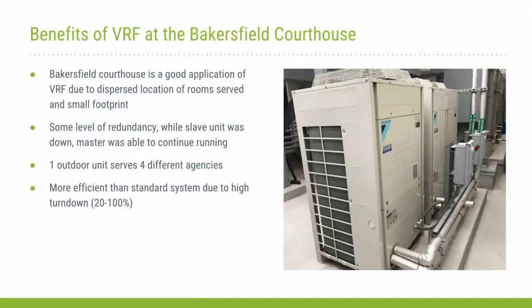So the benefits of the Bakersfield VRF installation have been due to the dispersed location of the server rooms and equipment rooms that it serves throughout the building, some on the first floor, some on the second floor. The runs for piping for a traditional system would not be a possibility in this location. One outdoor unit serves 4 different agencies: the U.S. Marshals Service, a couple of the bankruptcy and trustees, server rooms, security equipment rooms.